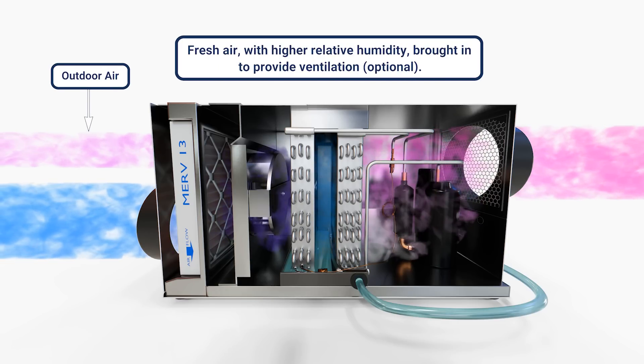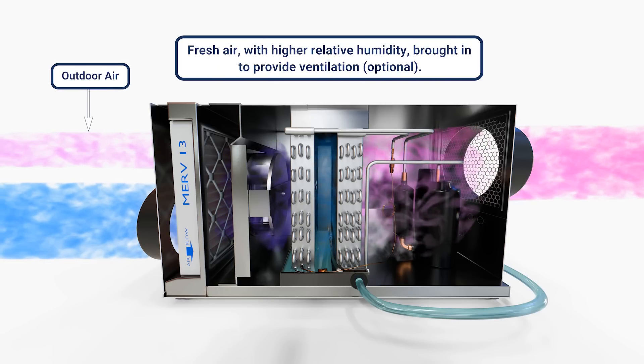Where is that moisture going to condense? At those vents — because that's the cold spot. It's always going to be the cold spot, and it needs to be the cold spot. So trying to warm up the vent itself generally isn't the best way to do it, unless you're doing something like a dehumidifier dumping that air into the supply duct, which helps warm it up and helps reduce the humidity. Make sure things like the dryer are properly vented and aren't leaking in the laundry room, because when that moisture makes it into the house, it doesn't leave until the air conditioner or dehumidifier removes it. Wherever possible, try to solve these problems by keeping moisture out in the first place.